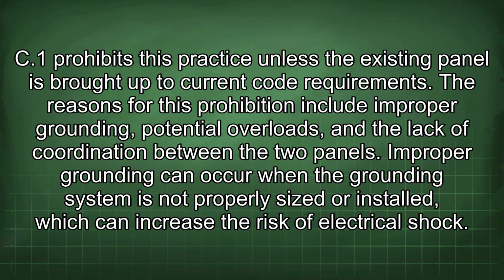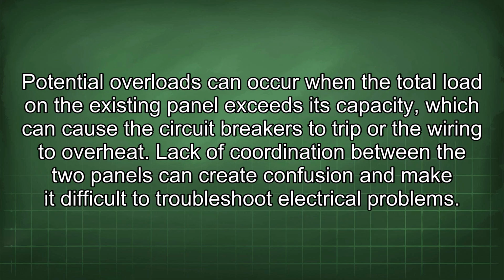The reasons for this prohibition include improper grounding, potential overloads, and the lack of coordination between the two panels. Improper grounding can occur when the grounding system is not properly sized or installed, which can increase the risk of electrical shock. Potential overloads can occur when the total load on the existing panel exceeds its capacity, which can cause the circuit breakers to trip or the wiring to overheat. Lack of coordination between the two panels can create confusion and make it difficult to troubleshoot electrical problems.